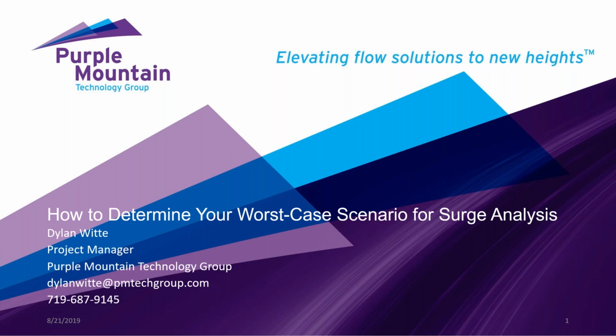That was an outstanding presentation, and I hope all of you enjoyed it. Bottom line is, everybody, you need to be doing a Waterhammer analysis. If you're not doing Waterhammer analysis, you need to be. The ASME B31.3 and B31.4 actually advise that you do look at Waterhammer. It's required by the codes, and also to evaluate the stress levels in the piping system. If you're not looking at Waterhammer, it is opening up so many opportunities for things to go very badly in the system, and it's really important to try and avoid those disasters of Waterhammer problems.